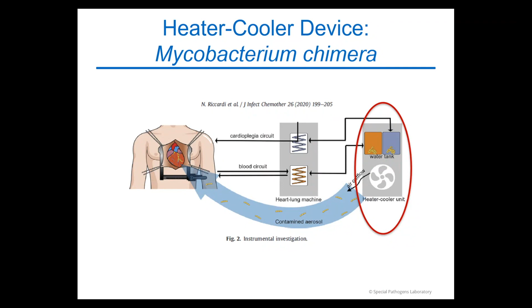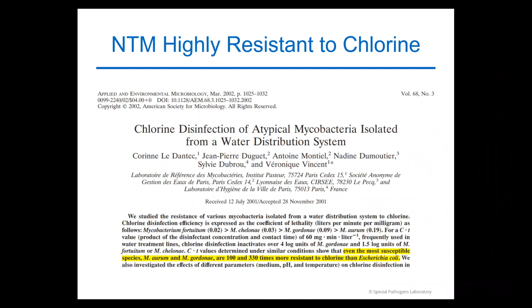One of the challenges with non-tuberculous mycobacteria is that they're highly resistant to disinfectants. This publication talks about these mycobacteria species being 100 to 300 times more resistant to chlorine than E. coli. So the message is, don't rinse equipment in tap water, including tap water that has Legionella.